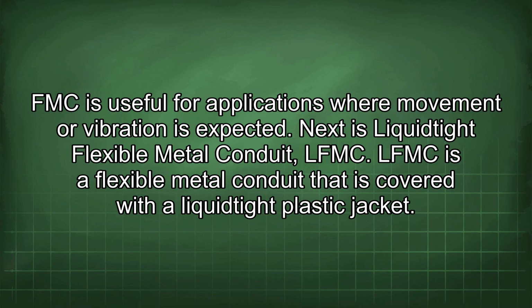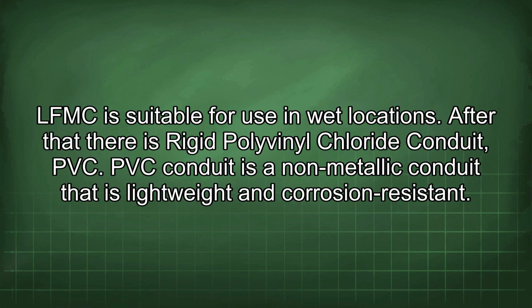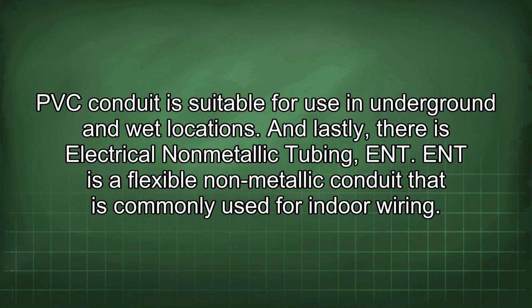Next is Liquidtight Flexible Metal Conduit, LFMC. LFMC is a flexible metal conduit that is covered with a liquidtight plastic jacket. LFMC is suitable for use in wet locations. After that there is rigid polyvinyl chloride conduit, PVC. PVC conduit is a non-metallic conduit that is lightweight and corrosion resistant. PVC conduit is suitable for use in underground and wet locations.